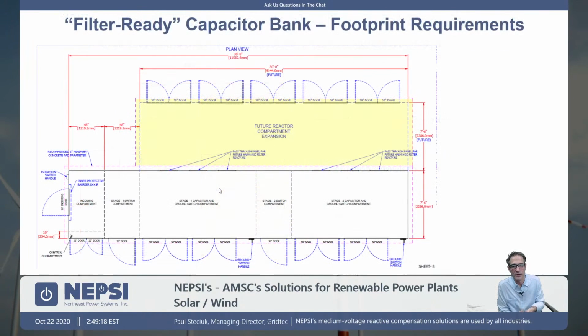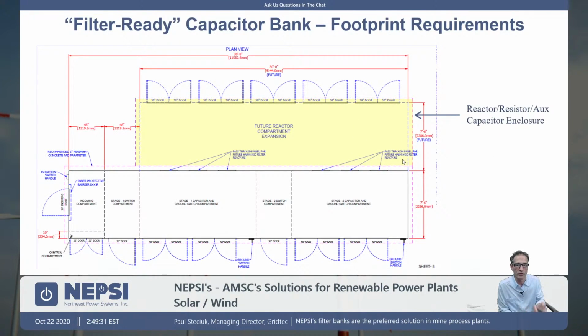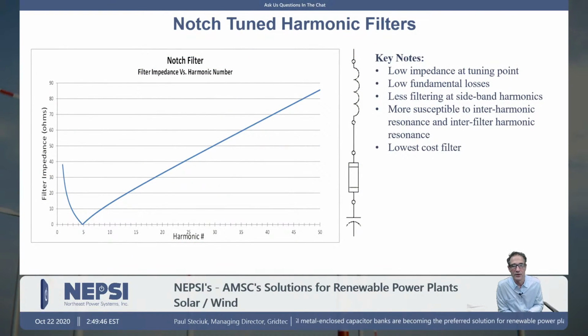So in the end, you have a pad requirement or a spacing requirement within the substation that includes the standard cap bank plus basically a double depth of that cap bank to include this yellow area. And that would be the requirement within the substation. So it's not a significant cost increase in the equipment because everything is an add-on. You're not adding a lot of cost to the substation because it's just a very small area, and you've got yourself covered. We can convert those cap banks to notch filters.